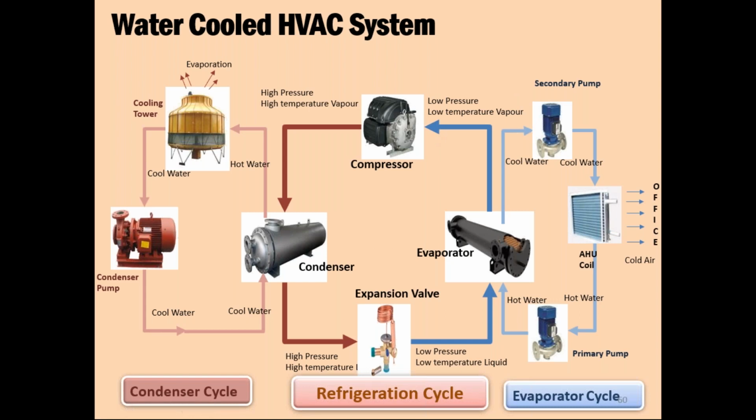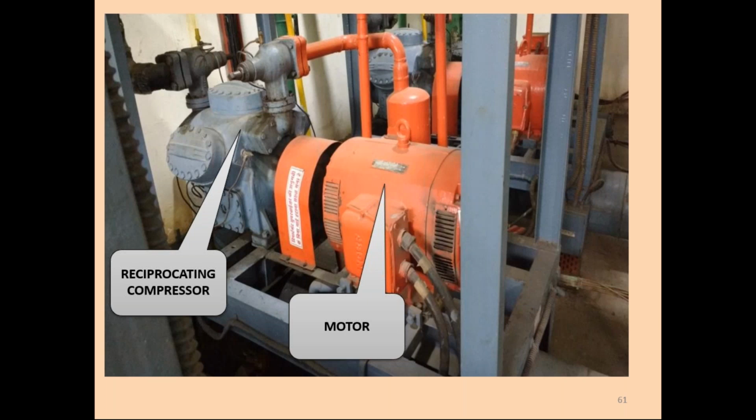So compressor power consumed versus the cooling tower, meaning the air cooled condenser fan power, will always have a higher output versus your water cooled system. So that is where the water cooled system is more popular and more efficient. When we see COP values or other values as a comparison, we will notice this.